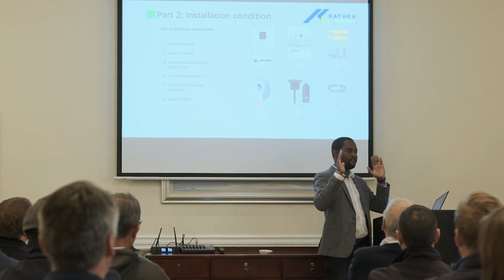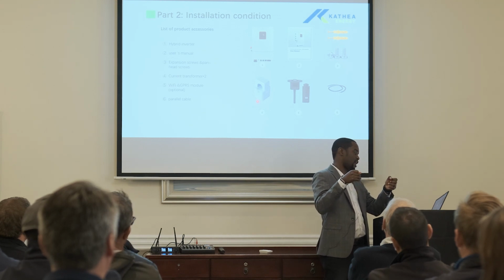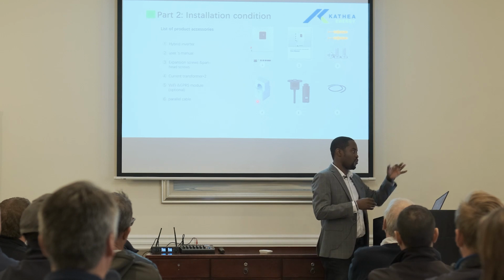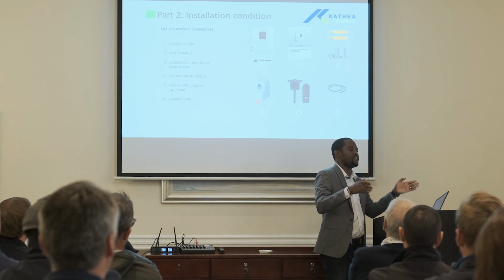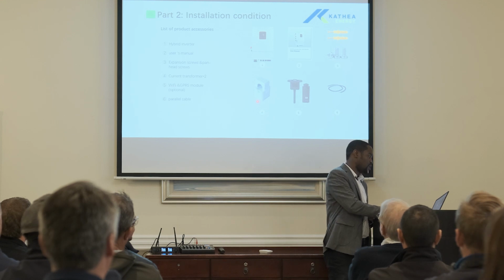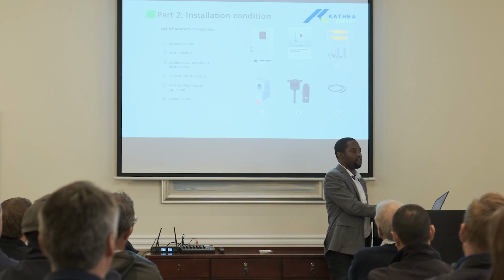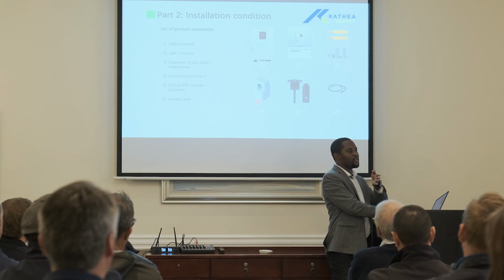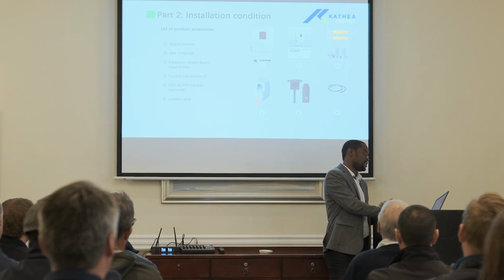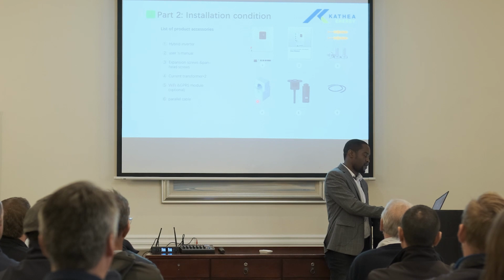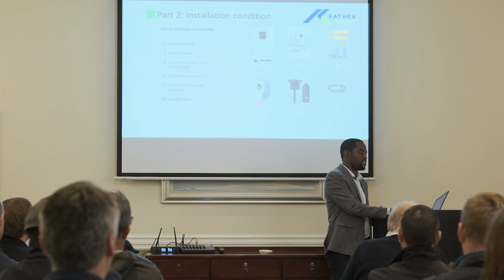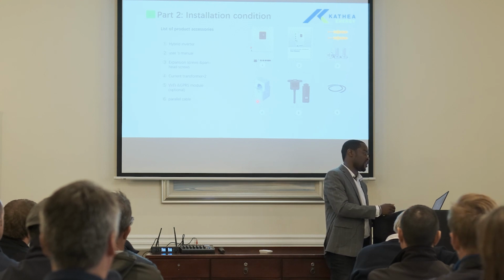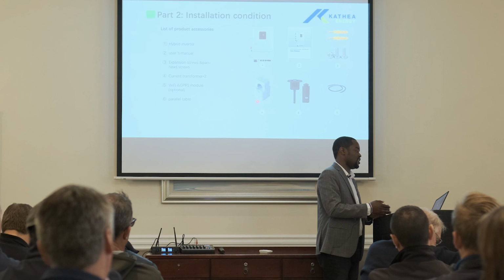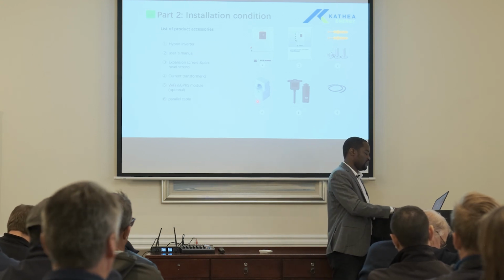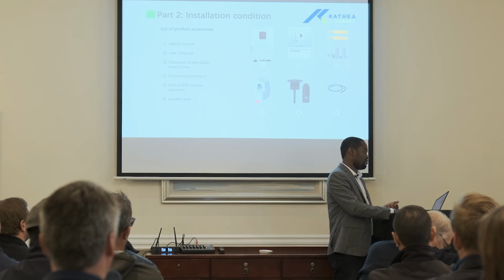We've got actually two transformers feeding to that. In the near future, in a few weeks' time, 8 weeks again, you should be able to hook CTs on each feeder. Then whether you're running on feeder A or feeder B, the inverter can do export control. And you can actually separately configure your export control limitation to say, okay, when I'm on feeder 1, I'm allowed feedback, but on feeder 2, I'm not allowed to feedback to grid. But that is a future capability. So it also shows that INVT are anticipating the market needs, and the R&D team is working actively to give us solutions that will improve our experience.